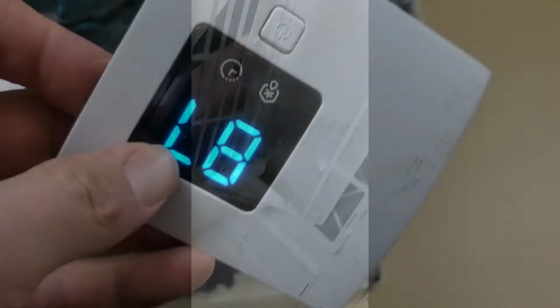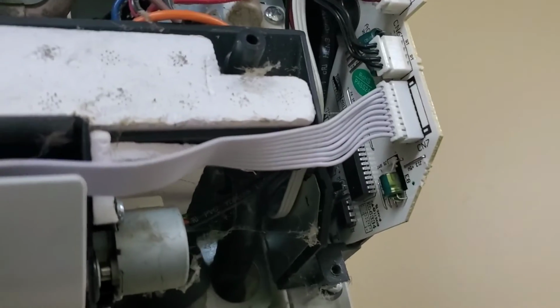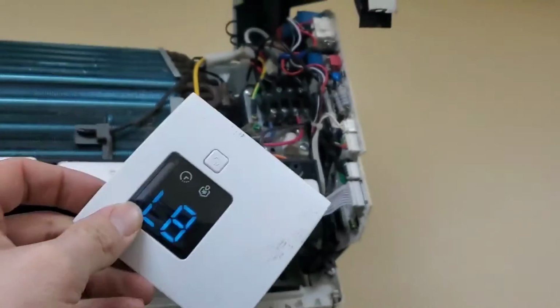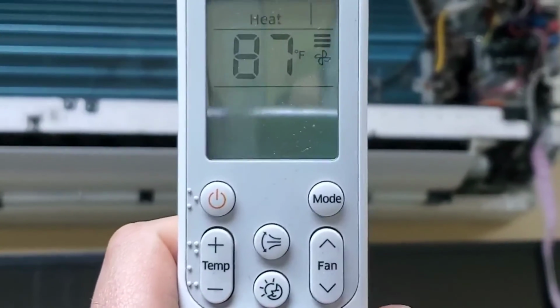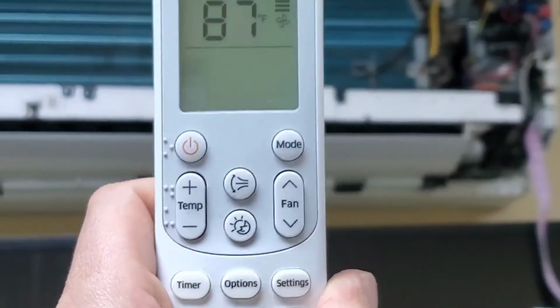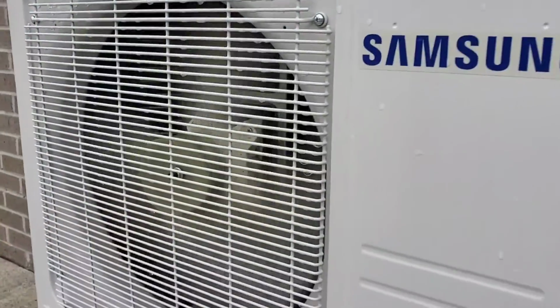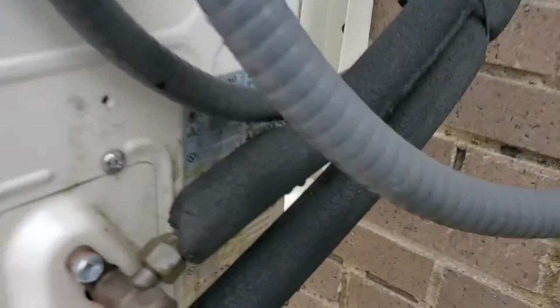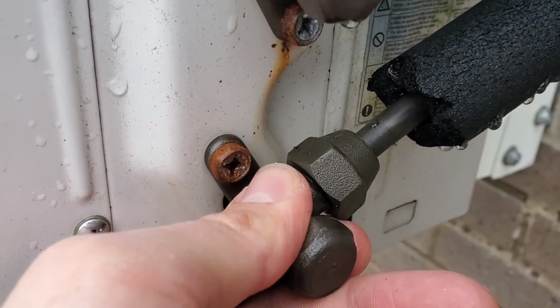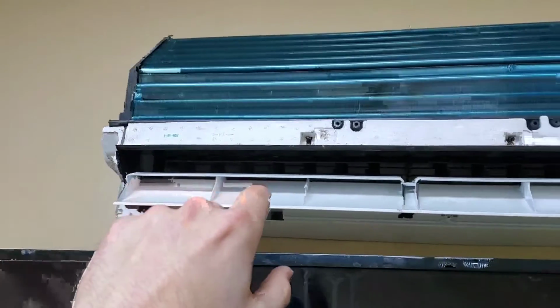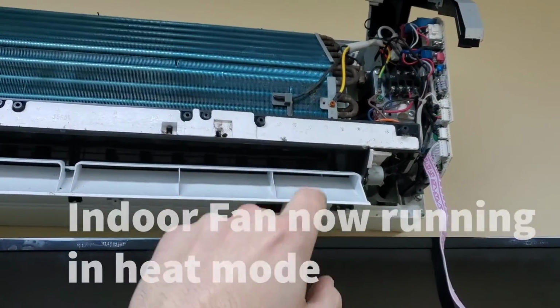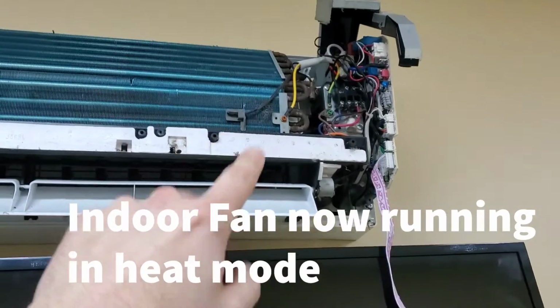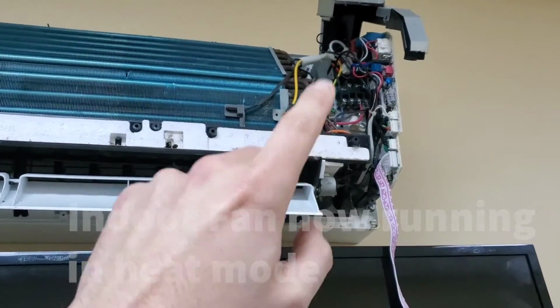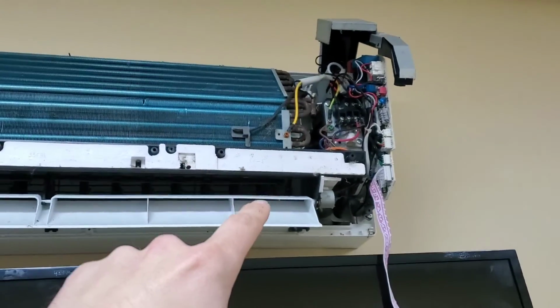So I take the display out and hook the display up. So that I've got it in heating mode, fan speed turned all the way up. Fan spinning. Hot gas line is very warm, so it's building up heat. Should release the indoor fan soon. So the fan is turned on, temperatures reach 99 degrees on the coil. So that fixed the problem. Error code E6, bad main PCB, indoor unit.